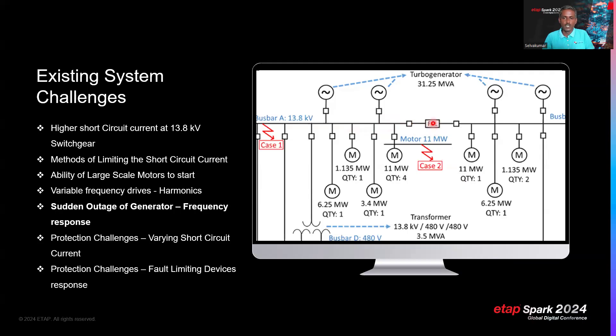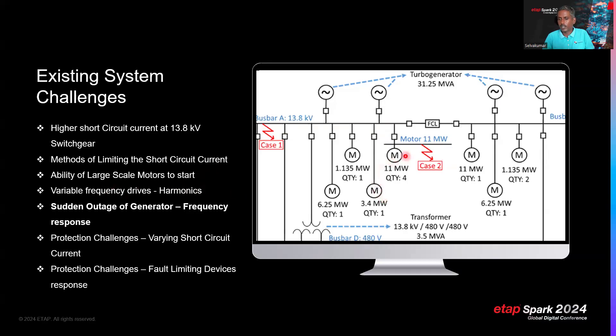A fault current limiting device such as an IS-limiter can be used to stay within 40 or 50 kA switchgear ratings. Another challenge is motor starting: large motors draw six to seven times rated current during starting, causing voltage dips on the 13.8 kV bus that impact other running motors. Additionally, variable frequency drives inject harmonics that may resonate with 13.8 kV cable capacitance, requiring detailed harmonic studies.